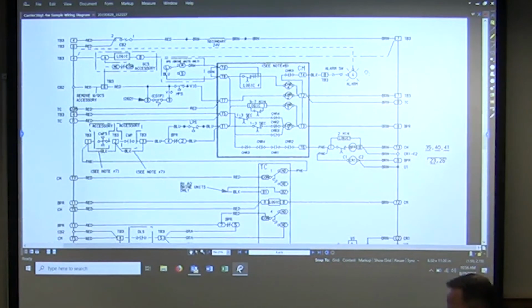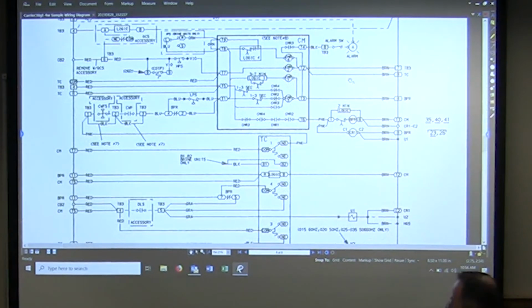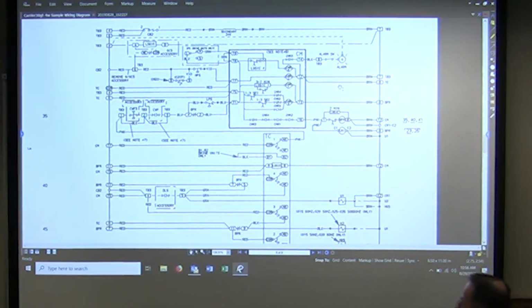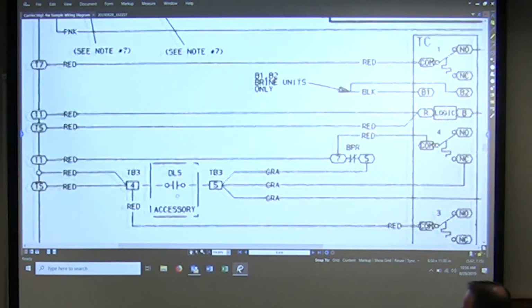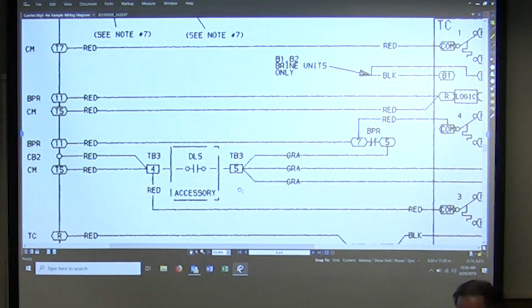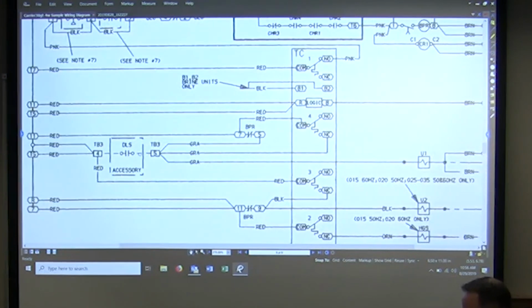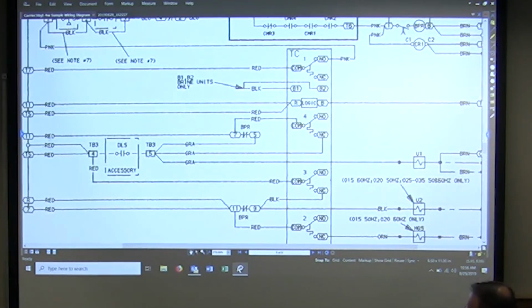Okay. The next one asks, how do I wire in a demand limit switch? That's the other accessory that's down towards the bottom. Okay, so down here in the bottom left of our page, 4 and 5. Do I need to remove the jumper? Okay, what does a demand limit switch do? If we look at this circuit, let me back it out a little bit. It powers the unloader. Okay, so I'm taking 24 volts. If I close the contact or put a jumper there, it comes straight over and energizes my unloader.